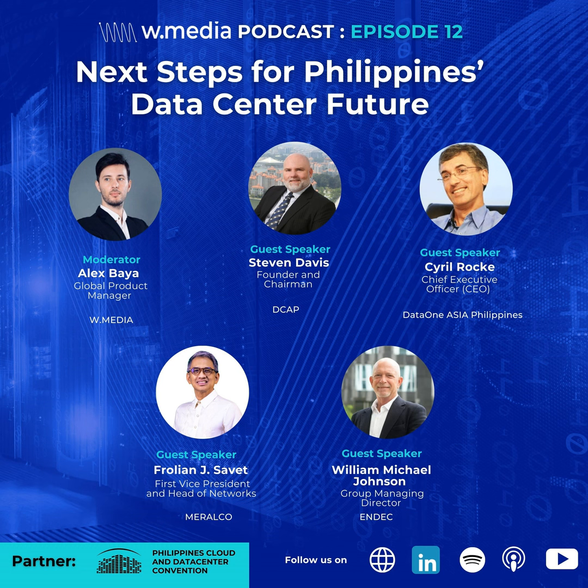Now the biggest challenge most of these data centers are going to encounter is they've already built space where a data hall is 280 racks. Well, once you put AI in, or 100 kilowatt racks, your 280 racks of 10 kilowatts turns into 28 racks. So you just architected your entire space, established your cooling system for the entire data hall to allocate equally across it, and you just consolidated that into a single 28-rack area. So the wasted money on space, architecture, revenue, and capabilities are all diminished at that point, based on a brick and mortar traditional data center.